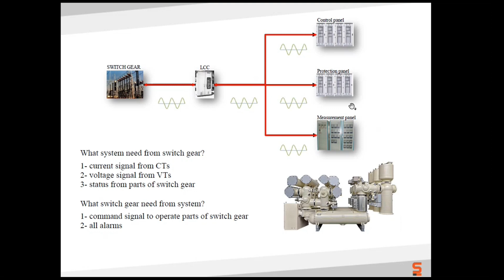The signal is distributed to all panels in parallel. As I said, to take the status of a circuit breaker here, you need various contacts, various NO/NC contacts - if you know a bit about these relays or contactors, you'd need 4 or 5 NO/NC contacts. From these NO/NC contacts of a breaker, you have to hardwire to the LCC, to the control panel, to the protection panel, to the measurement panel. Again hardwiring is required through cables. So a lot of cable, and cable laying is a big task in the substation.